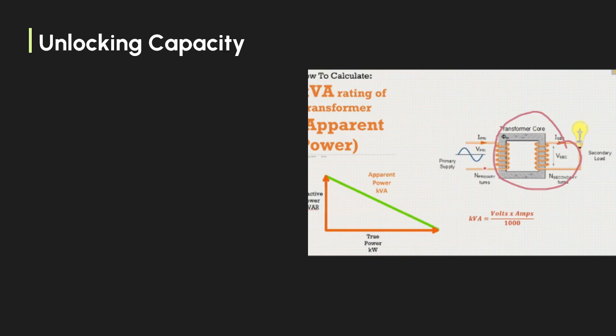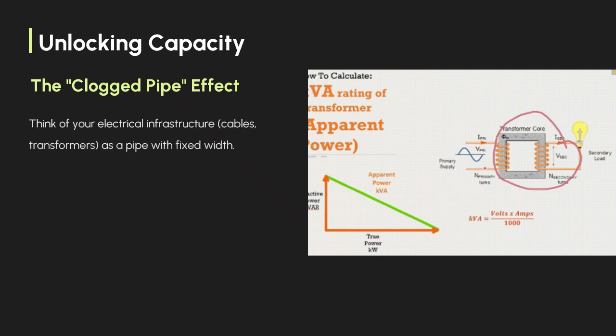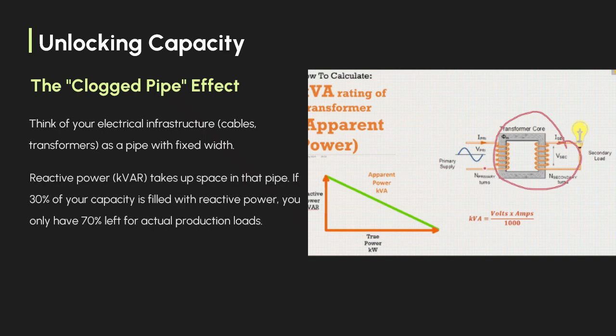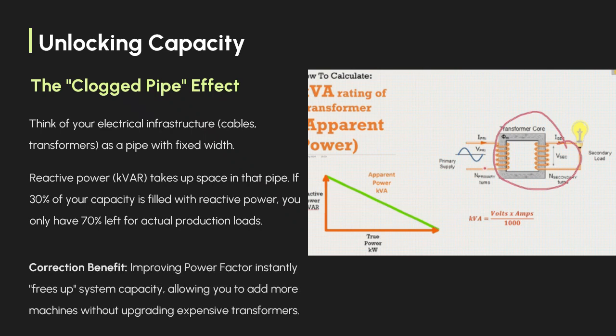Unlocking capacity. One of the biggest impacts of a low power factor is system capacity loss. Think of your electrical infrastructure, such as cables and transformers, as a fixed width pipe. The reactive power takes up space in that pipe. If 30% of your current flow is reactive, then 30% of your total infrastructure capacity is unavailable for productive loads. By improving the power factor, you instantly free up this valuable capacity, allowing you to add new production machinery without the enormous expense of upgrading your main transformers.